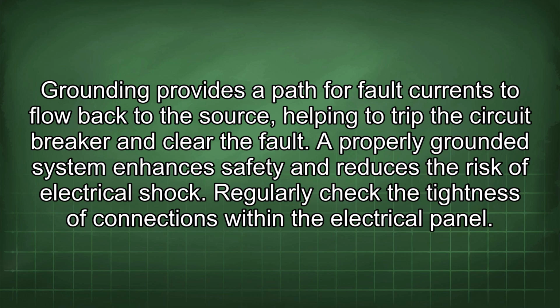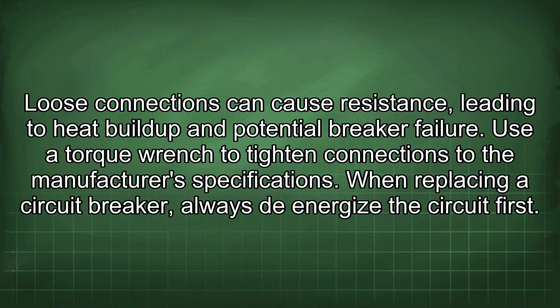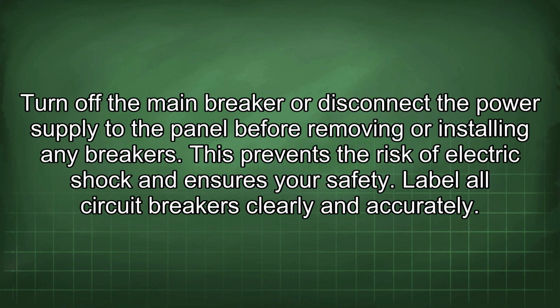Regularly check the tightness of connections within the electrical panel. Loose connections can cause resistance, leading to heat buildup and potential breaker failure. Use a torque wrench to tighten connections to the manufacturer's specifications. When replacing a circuit breaker, always de-energize the circuit first. Turn off the main breaker or disconnect the power supply to the panel before removing or installing any breakers. This prevents the risk of electric shock and ensures your safety.